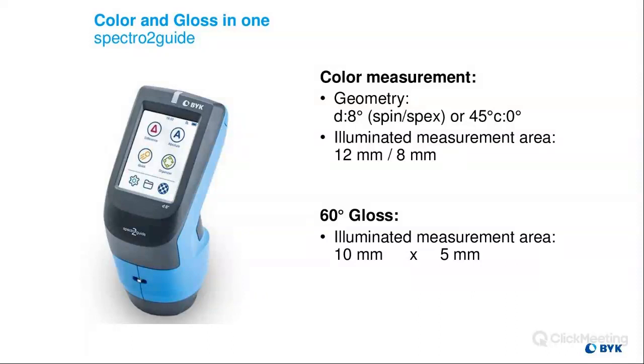Everyone who needs to measure the same target color can be operating off of the same standard, rather than having to have physical standards and ship them around, and all those standards are going to inevitably differ from each other somewhat, and the measurements with the various instruments are going to differ on those standards somewhat. With this instrument, because of the excellent inter-instrument agreement, you can use digital standards where everybody's working on the same target, which makes things a lot easier when you have a big supply chain.